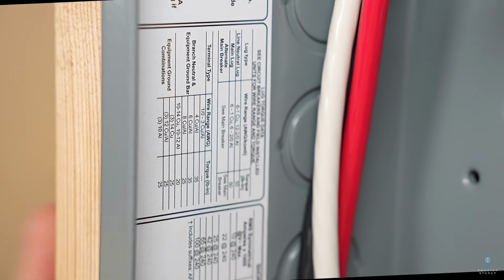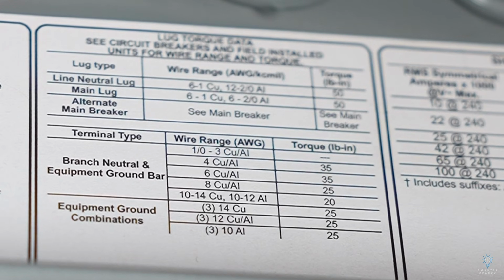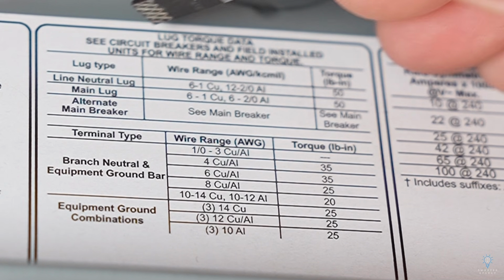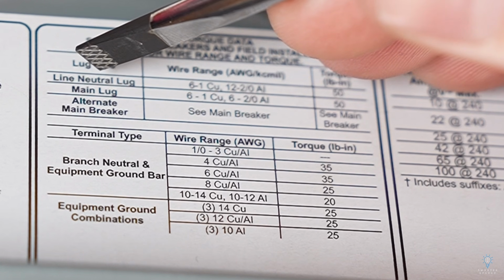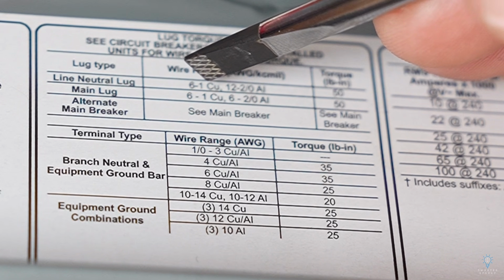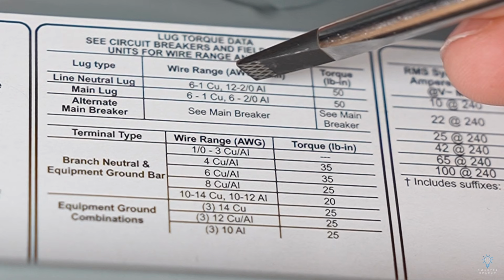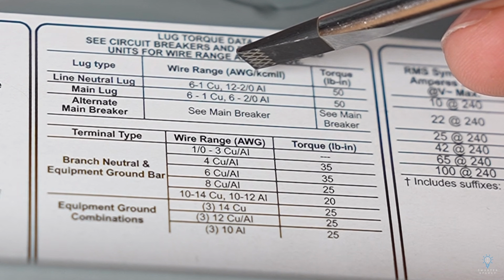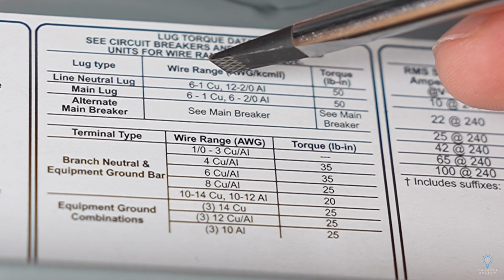So I've done my best to zoom you in here on this sticker, and maybe I can rotate this in editing. Notice here it says lug type, line and neutral lug is 6 gauge to 1 gauge copper, or 12 gauge to 2/0 gauge aluminum. That's actually a really weird wire range.